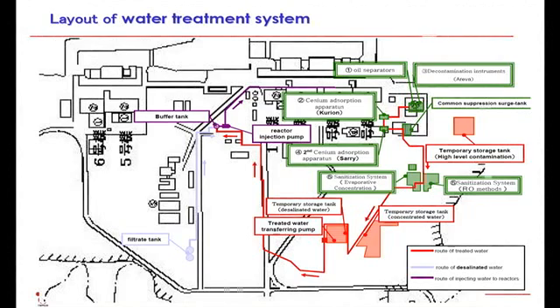The water is pumped up and goes through the oil separators, then cesium is adsorbed. The water treated by water treatment facilities such as Kurion, Areva, and SARRY goes through the desalination system where chloride ion is removed. Then it is reused as the processed water for the reactor. This is the overview of the system. As for the waste sludge, it is now kept in the storage tanks in the process main building. In addition, 2,800 cubic meters of temporary storage tanks for high-level contamination has been installed and is ready for storage.